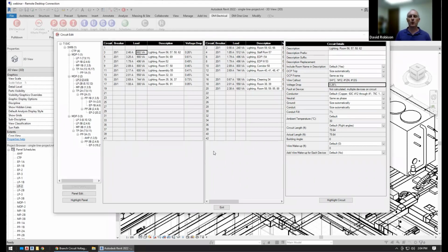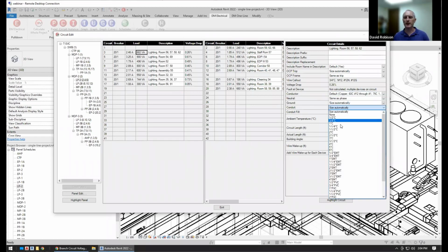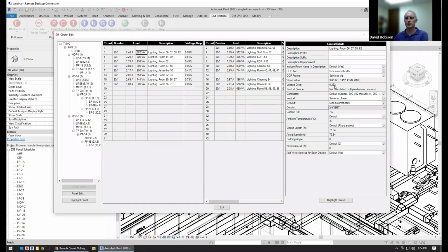And if you have a mix, the size of the conduit isn't going to tell you exactly what the material is. The way we have that set up in our software is that you choose the conduit size. We've got these defaults, this is the EMT PVC swapping. We also have specific EMT and PVC tables as well. So you could specify a specific size for the conduit and a specific material, and then it'll include it in that wire callout. If I wanted to specify 3/4 EMT, or 3/4 PVC, it'll actually change the wire callout, so it's clear that that's what's being indicated there.